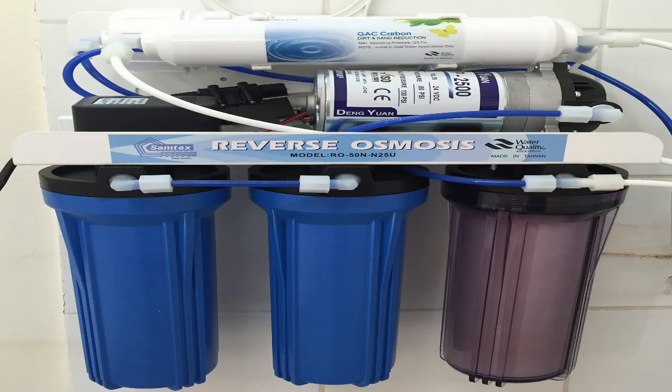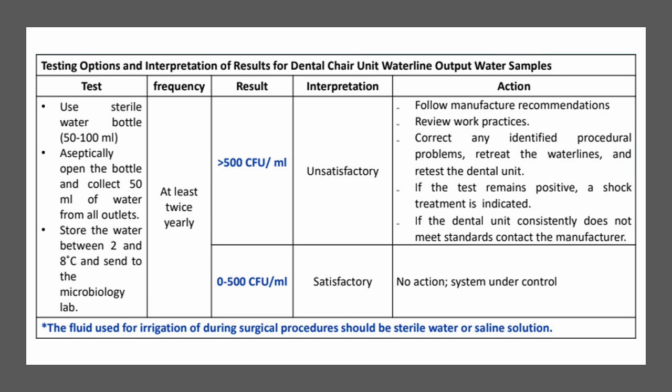The water reservoir for the clinic is separated from the municipal water supply. It shouldn't go directly to the dental clinic. You should use filters. The filters are used to keep the microorganisms out of the water, and these filters should be changed according to the manufacturer instructions. Follow the right procedure in testing the water lines in the dental clinic. Each dental clinic should be tested twice a year. So, test the dental unit water and treat it if the bacterial count exceeds the CDC recommendation.